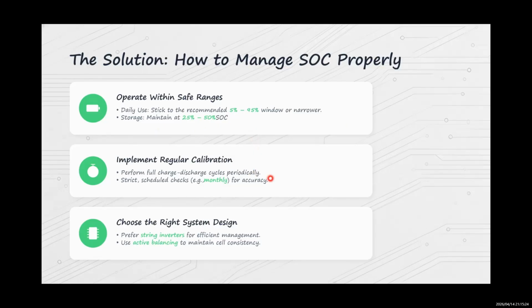Second, implement a regular calibration schedule, normally monthly calibration. Third, choose the right system design that helps you manage SOC effectively, like using a string inverter to manage each battery rack respectively, and adopt active balancing solutions. So get these 3 things right, and you will be well on your way to a healthy and profitable system.